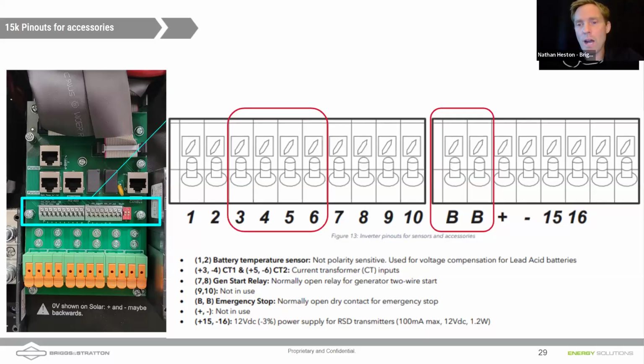B and B are also highlighted. They're in positions 11 and 12. That is for your rapid shutdown device, right? So code is going to require you to have an accessible disconnect on the system, which will shut that system down from the outside in the event of an emergency. So that's your emergency stop button.